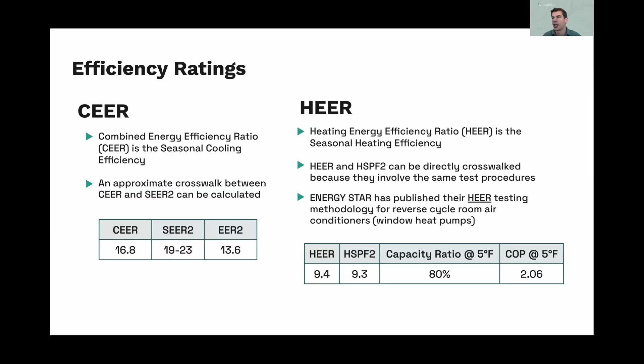Then there's HEER, heating energy efficiency ratio, which is the equivalent heating performance. HSPF already exists for mini splits, but unfortunately these products aren't rated to an equivalent HSPF rating. They have their own different efficiency metric, which is HEER. It's a little easier to translate from HEER to HSPF, so I'm introducing that here. HEER is the heating efficiency of this product category, while CEER is the cooling efficiency.